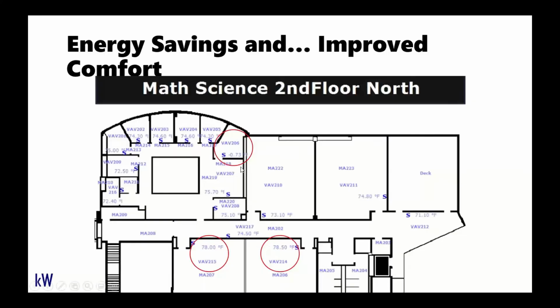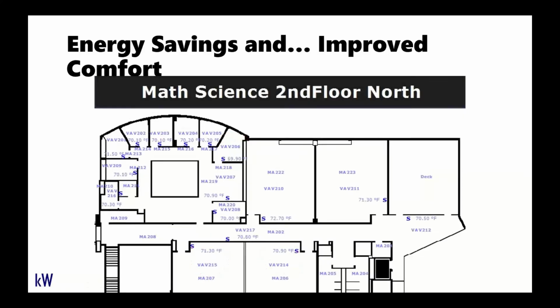So again, as part of the project, we identified this deficiency compared to how these systems were supposed to be running. We worked again with Climatech to identify the root cause, which was some bad sensors and control data throughout the space, and corrected it as part of the final project. And you can see in this post-retrofit data that the proper signal from this room has been restored, and the temperatures have been brought down in line with the rest of the building, as well as the typical comfort range. And so we've achieved with this project energy savings, as well as improved occupant comfort, and hopefully some reduced burden on the maintenance staff through fewer hot and cold calls.